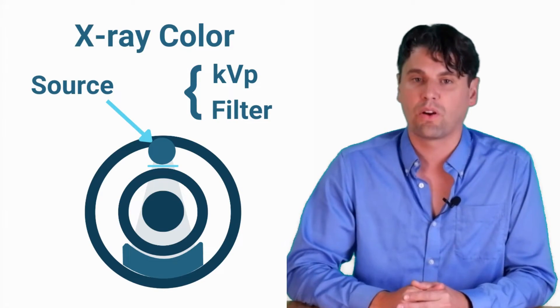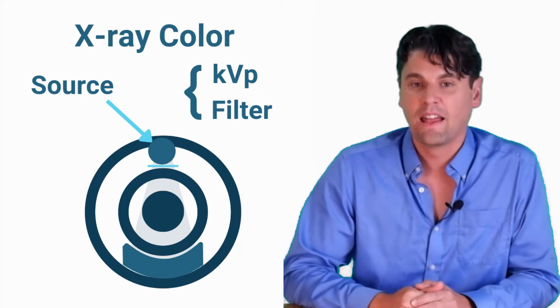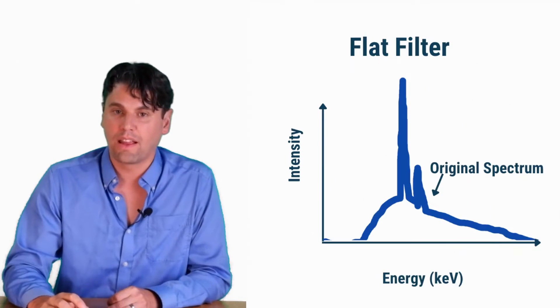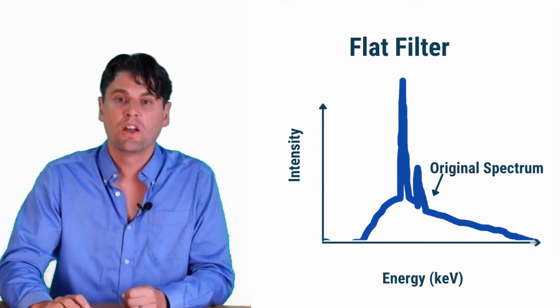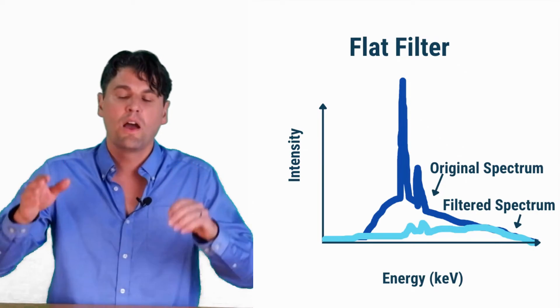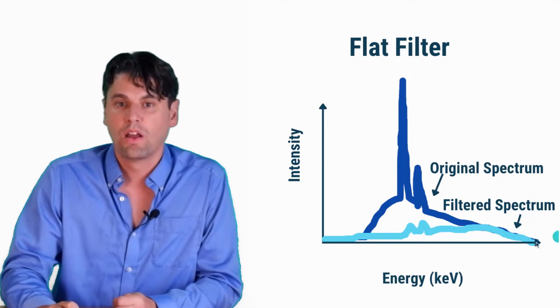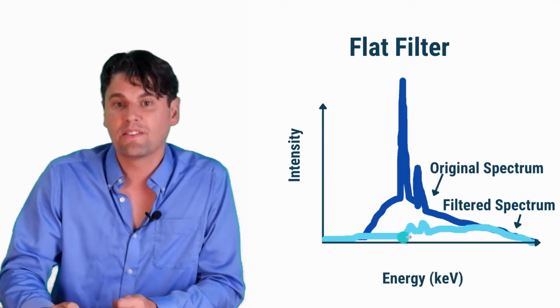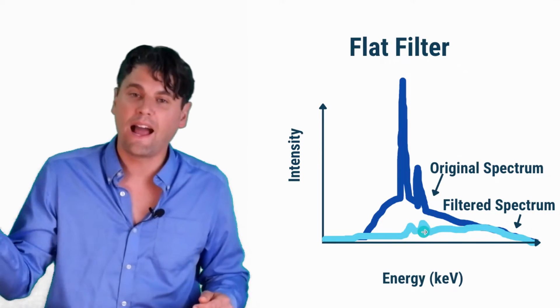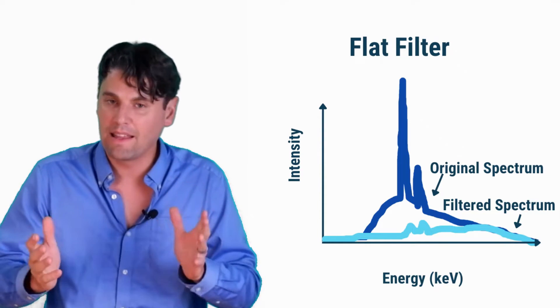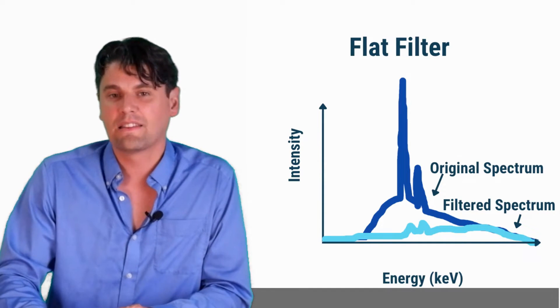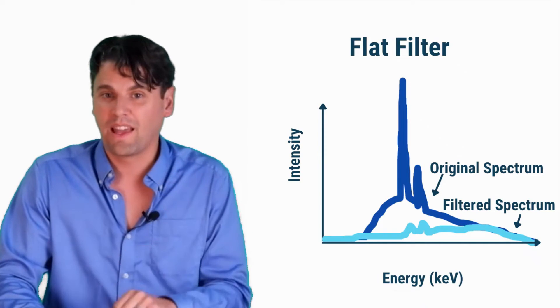The second way is by changing the filter placed after that x-ray tube. If you start with a beam and then put something in there such as a tin filter, you're going to preferentially stop the lower energy x-rays more, so you get many fewer x-rays through but the average energy of your x-ray spectrum moves to a higher energy. You can also combine these two ways — either changing the KVP or using a filter.